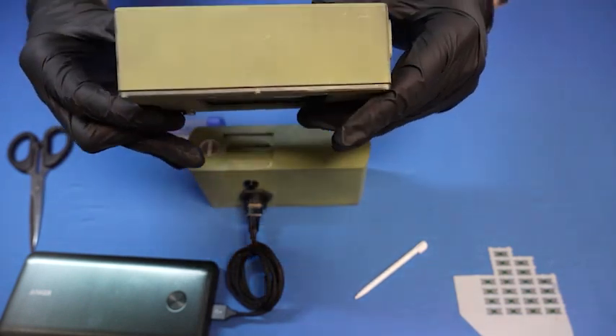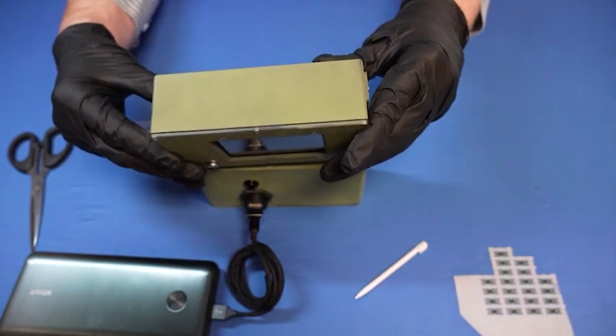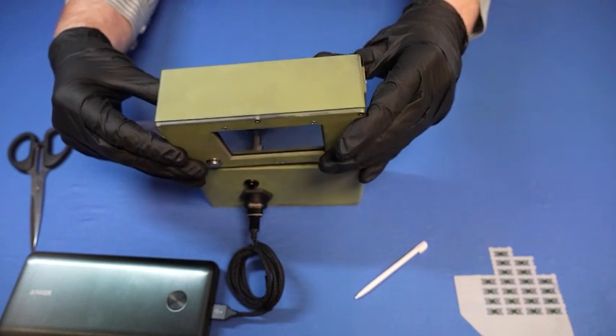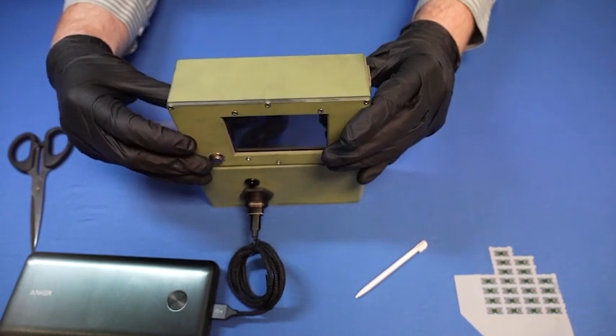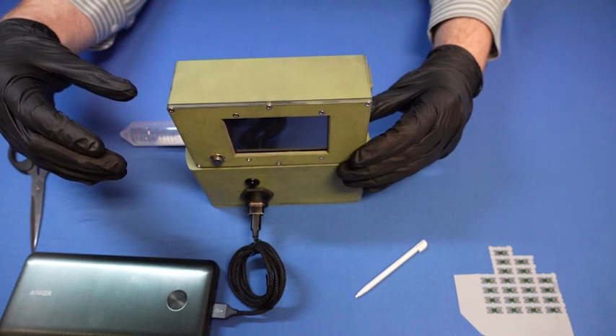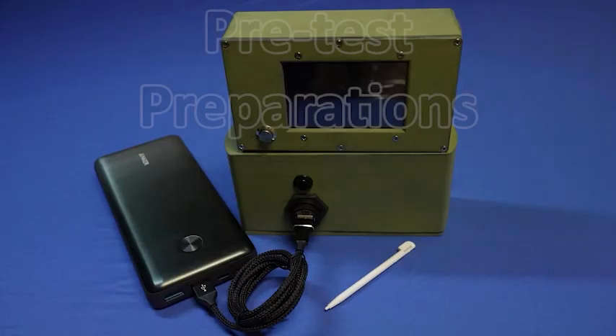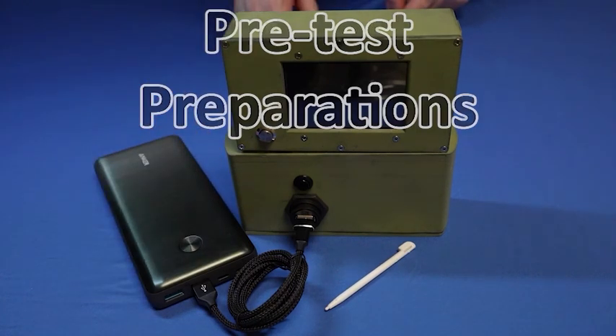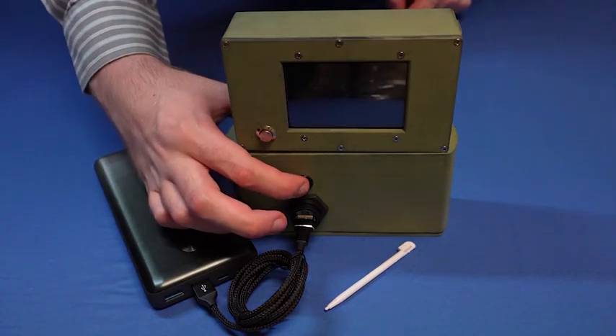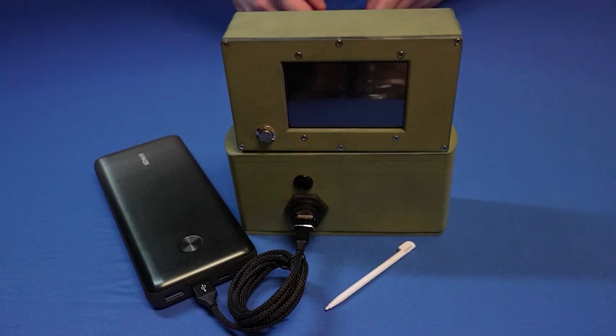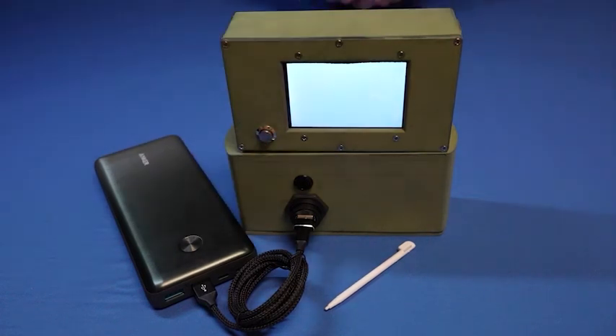Put the CDTT main device on top of the lab sled so that the electrode enters the bridge of the lab sled cup. Ensure the adapter above the electrode does not get wet. Pre-test preparations. Use the black button on the lab sled to begin stirring the sample. Turn the CDTT main device on by pressing the silver button. Wait for the screen to display the user interface.